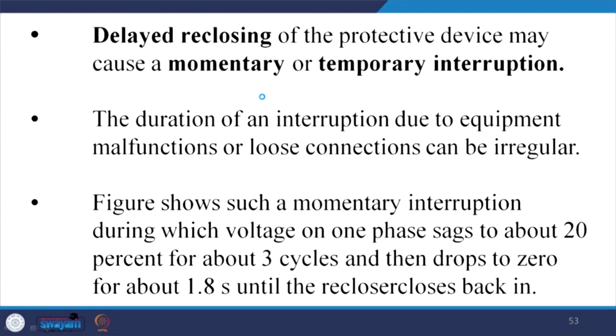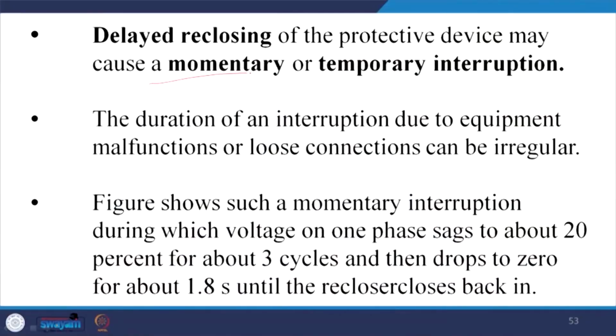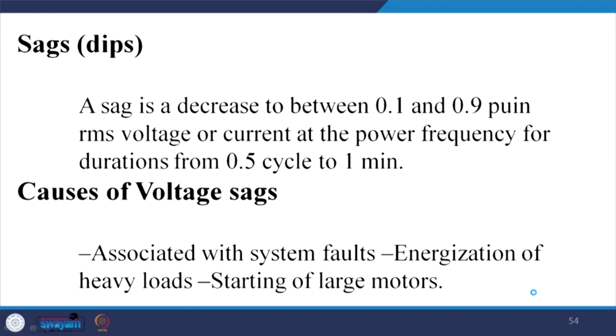So, we conclude that delayed reclosing of protective devices, for example an isolator or circuit breaker, may momentarily or temporarily give an interruption. The duration of an interruption due to equipment malfunction or loose connection can be irregular, and we may lose data. The previous figure shows a momentary interruption during which the voltage on one phase sags about 20% for about 3 cycles, then drops to 0 for about 1.8 seconds and recloses back.